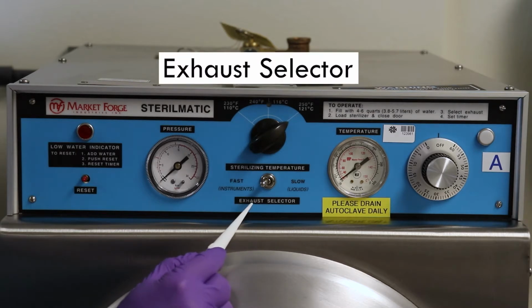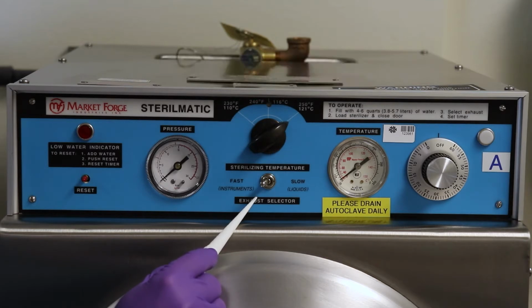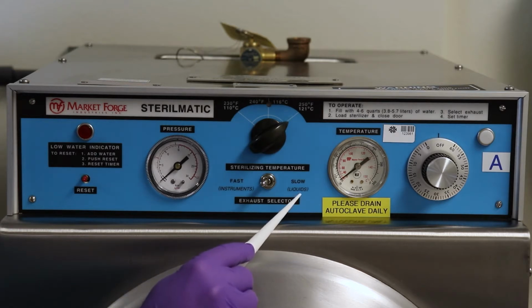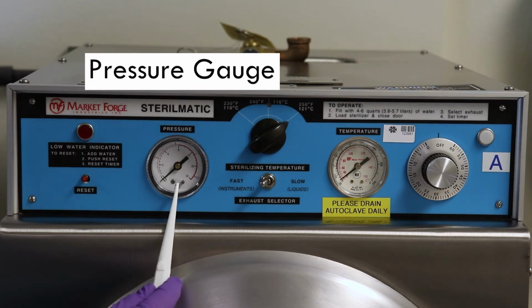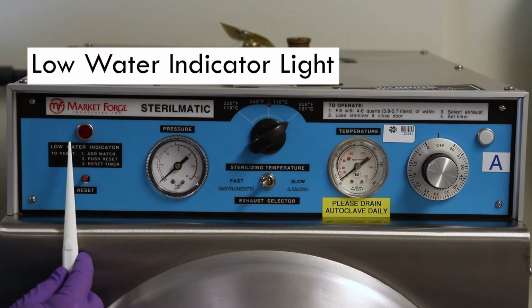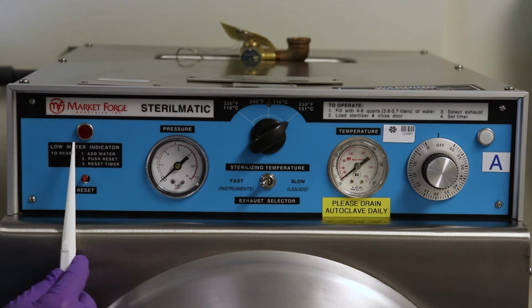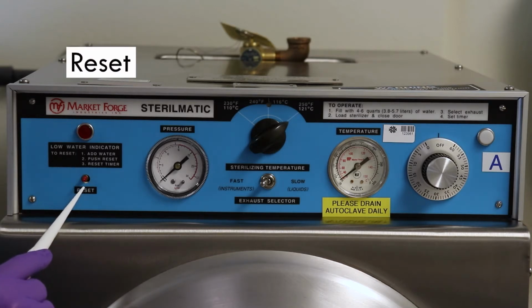The exhaust selector, which allows you to select whether you want, when depressurizing, a fast exhaust cycle or a slow exhaust cycle. We use fast exhaust for items like glassware and other solids, slow for anything that has a liquid inside of it. Then we have the pressure gauge, which shows the pressure inside the chamber. The low water indicator light will turn on when there is not enough water inside the chamber to continue with a proper sterilization. When this turns on, you will need to wait for the chamber to depressurize, add more water, and then hit the little reset button here, and then restart the cycle.